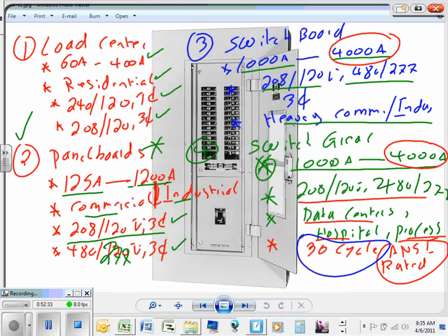If it doesn't trip within 1/20th of a second, you know what happened? Everything here will be burned. That's how they rate them. 3 cycles, all these circuit breakers are rated for 3 cycles. So who cares, Brad? When I do my coordination, I have to take this into consideration, Spencer. Otherwise, if I allow the short circuit to sit here more than 3 cycles, I have just fried this panel.